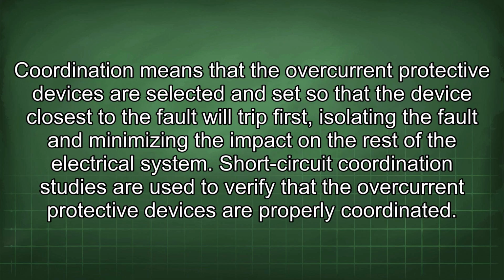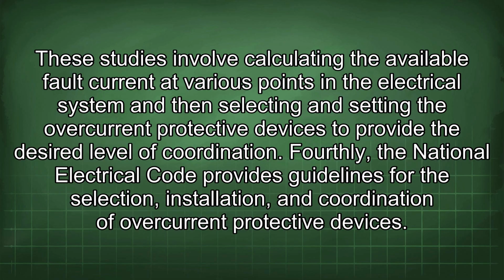Coordination means that the overcurrent protective devices are selected and set so that the device closest to the fault will trip first, isolating the fault and minimizing the impact on the rest of the electrical system. Short-circuit coordination studies are used to verify that the overcurrent protective devices are properly coordinated. These studies involve calculating the available fault current at various points in the electrical system and then selecting and setting the overcurrent protective devices to provide the desired level of coordination.